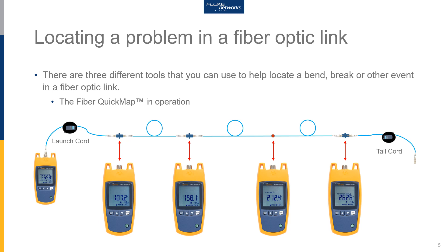So the link failed with the optical loss test set, but the instrument was able to tell me what problems I had and where they were. In this case, I'll clean the connector, I'll redo the splice, and then I can go back to my optical loss test set and certify the link again with all the problems now solved.